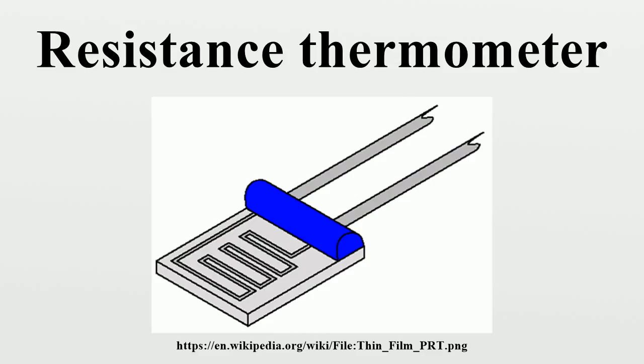Thin film elements have a sensing element that is formed by depositing a very thin layer of resistive material, normally platinum, on a ceramic substrate. This layer is usually just 10 to 100 angstroms thick. This film is then coated with an epoxy or glass that helps protect the deposited film and also acts as a strain relief for the external lead wires.